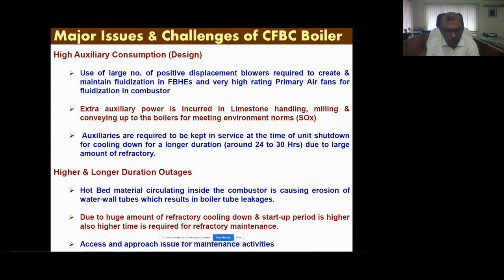Then there are higher and longer duration outages. The hot bed material is at 850 degrees temperature and causes erosion in the walls, which mainly results in boiler tube leakages, and that causes forced outages. Due to the huge amount of refractory, the cooling down and startup period is longer, and the time required for refractory maintenance is also longer. And as already explained, since there are a lot of areas in the combustor and the temperature is high, you cannot approach for maintenance. That is one major constraint. So this also results in higher outage durations, which directly affects the plant availability.